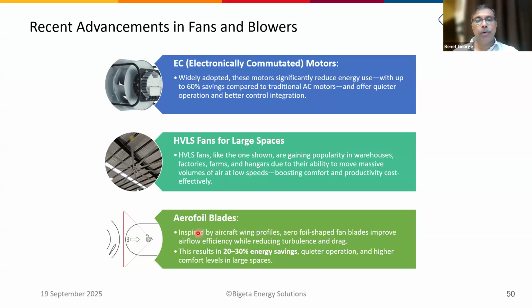Similar to BLDC fans, electronically commutated motors will reduce the energy consumption, and in some cases 60% savings is achieved. Basically, this can be retrofitted in existing AHUs and cooler applications mainly. Second is the high volume low speed fan for conditioning large spaces. Instead of a large number of wall mounted fans or other fans, you can have large high volume low speed fans for a large space. This reduces the energy consumption. Then aerofoil designs also reduce the energy by 20 to 30%.